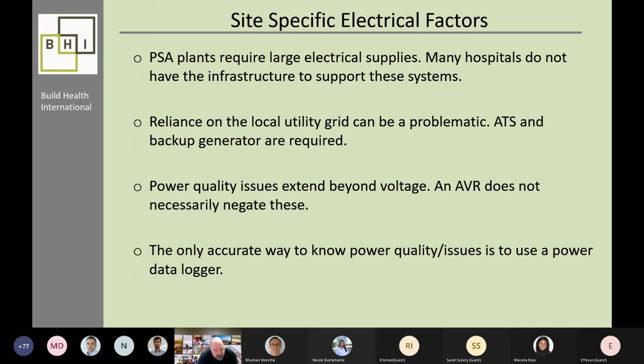They also think that it is only an issue of voltage, and that is not the case. The issues of power quality extend way beyond voltage. An AVR, which is an automatic voltage regulator, does not necessarily fix these issues. There are some issues that an AVR can address, but because it's a mechanical device that responds, there's a lag time. And depending on the power quality, sometimes AVRs can't address it, and they can't address issues of frequency, fluctuation, or harmonics. The only way to know what power quality issues you're dealing with is to use a power data logger on the system for a period of time, a minimum of 48 hours. So that's attached.